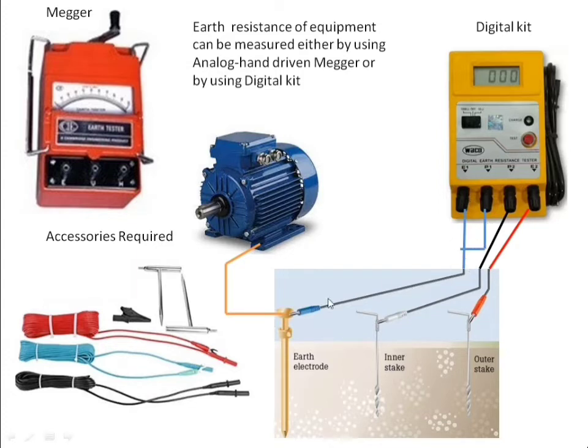Next, let us see the digital kit. It consists of 4 terminals: C1, E1, C2, E2. C1, C2 are current terminals, E1, E2 are voltage terminals. See the connections. First, C1, E1 are joined together and connected to the main rod whose resistance is to be measured. Then C2 is placed 100 feet away from the main rod, and E2 is placed between the main rod and C2, that is, 62 feet away from the main rod.